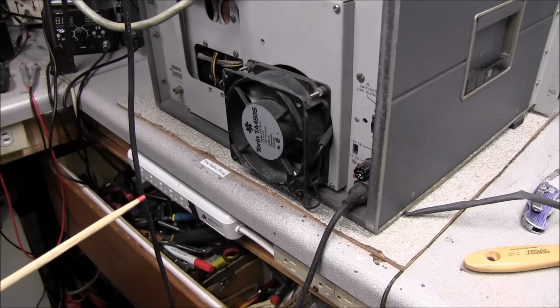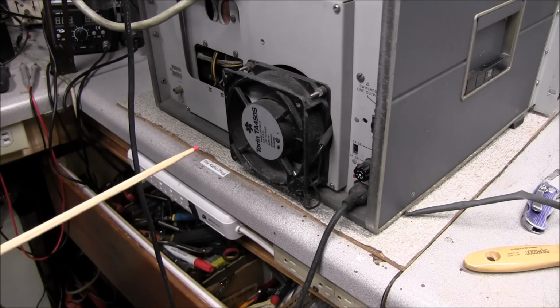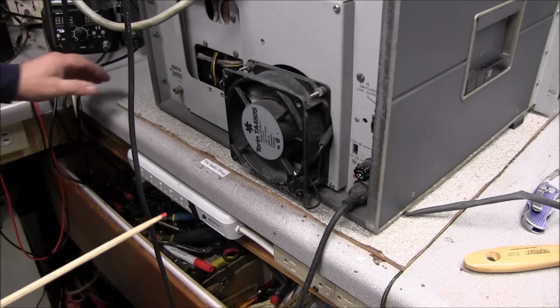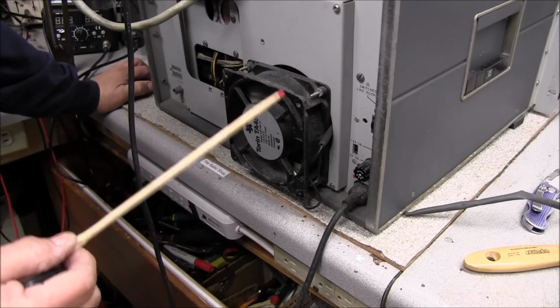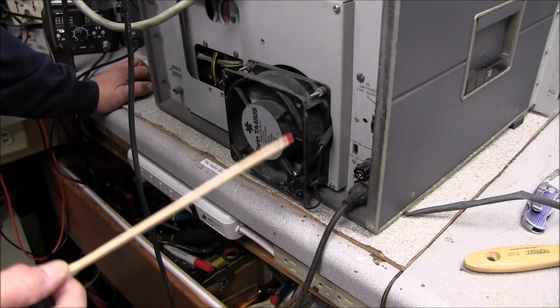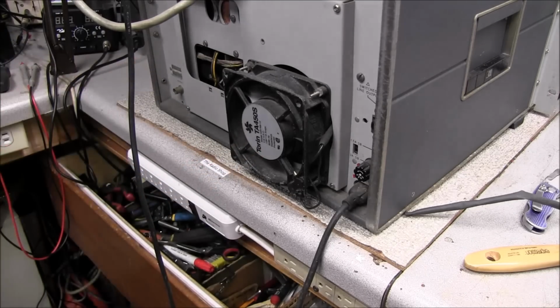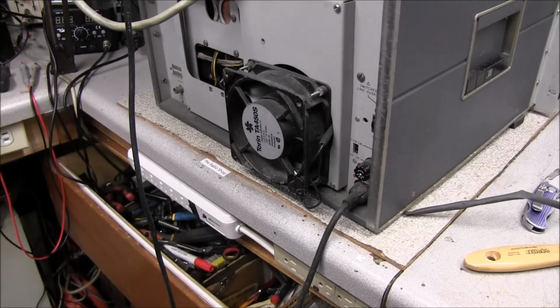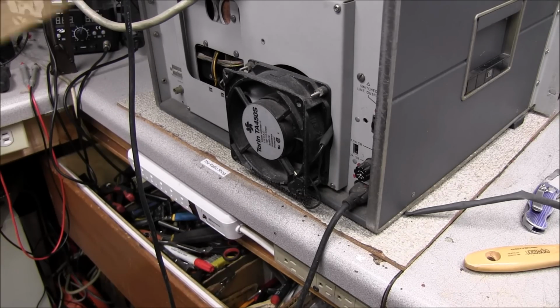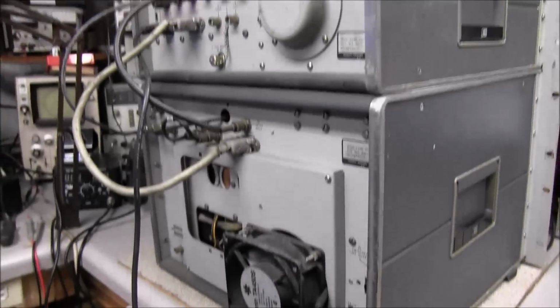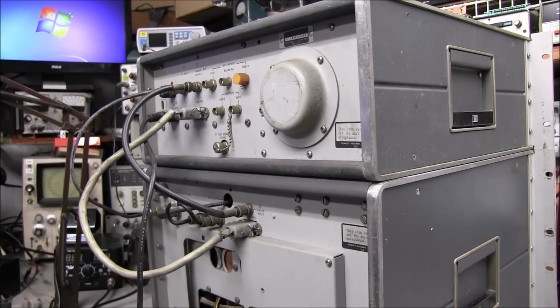I'm not sure what the original one looked like, but maybe we can go online and find some pictures of this and find out just what type of fan that HP did run in this. I have several that would probably fit in here like it's supposed to, but I'd like to get something close to the original. I think what I'm going to do now is go ahead and move the RF deck out and get a look at this display unit and see what's going on in it before we try to even power it up. And like I said, we already know that the RF deck has a blown fuse, so we need to determine what caused that fuse to blow.